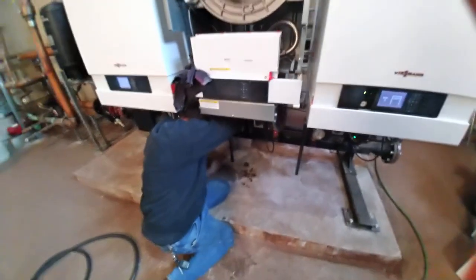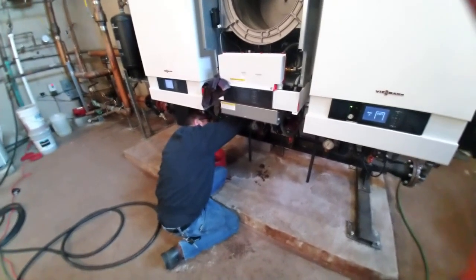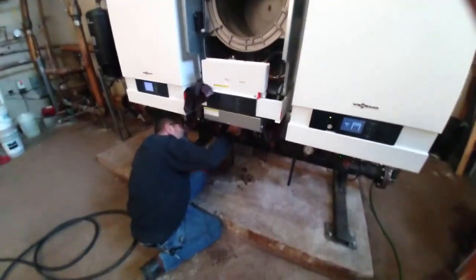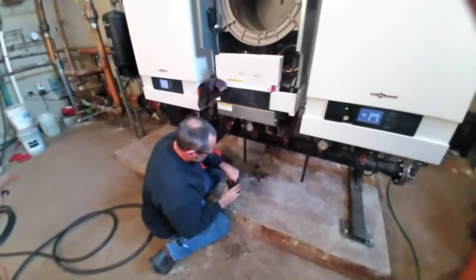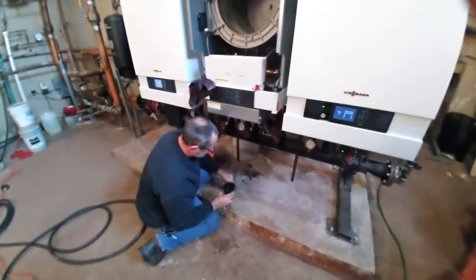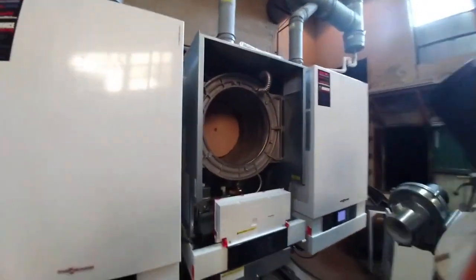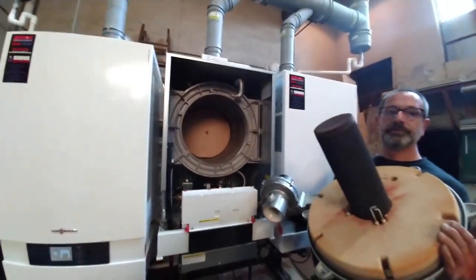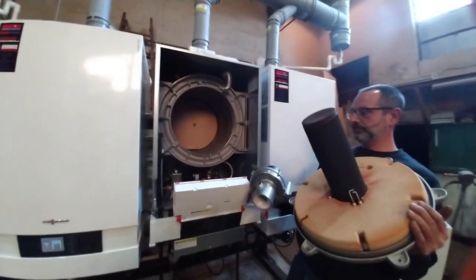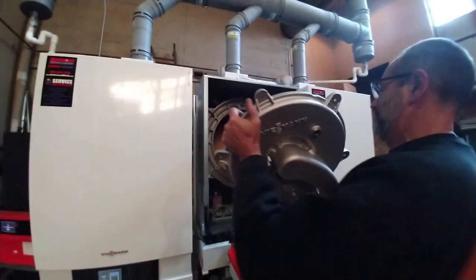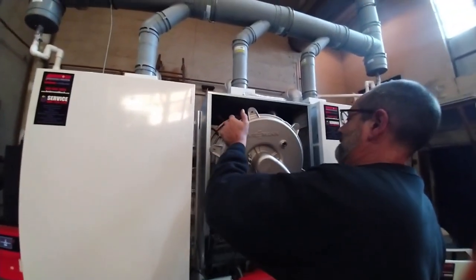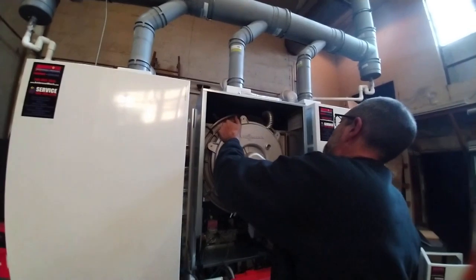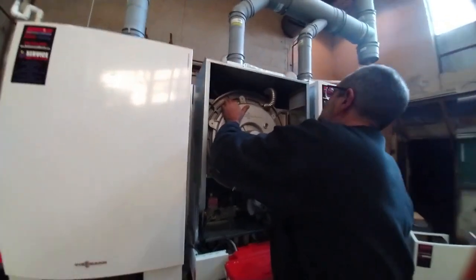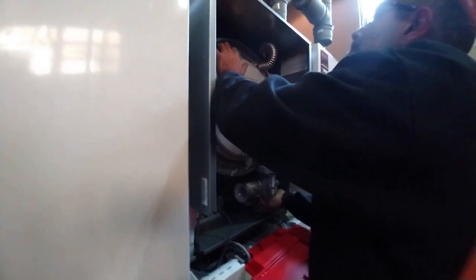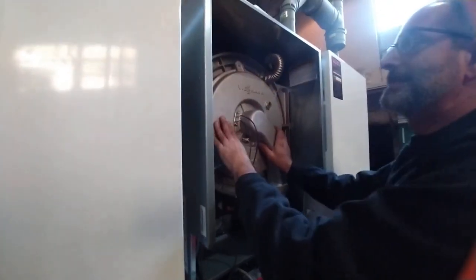And now's a good time to do the cleaning of the trap. Anything we may have flushed down out of the heat exchanger would have gone into the condensate trap, and we want to make sure that that's nice and clean. So now that we have the rear refractory mounted again, we're going to put the front plate with the front refractory, burner and combustion fan back in place. We'll make sure it seals properly. We'll tighten the 6 bolts, and we'll reconnect the wiring and the gas line, and then we should be good to fire it up again.